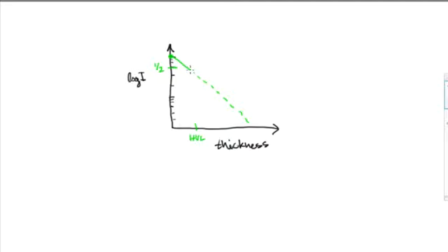What happens is the beam hardens. So as it goes down to the next half-value layer, where you're going to get down to a quarter of the beam, it's not going to follow that line. It's actually going to take longer for it to get there. I'm exaggerating this, but let's say it goes like this. Then the next half-value layer is going to be even longer, and so on. So it's going to kind of even out like this. The idea here is that it's hardening as it goes down.